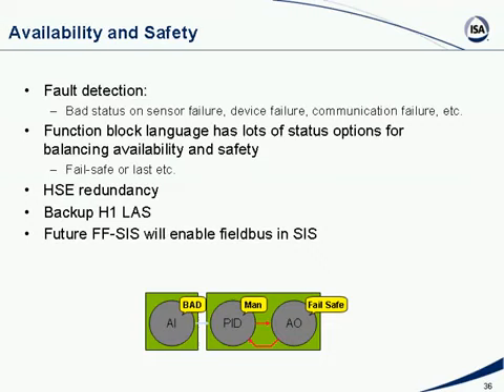Another thing is that usually you have redundant interface cards for field bus, at least for the buses with control. If there's a pure monitoring segment, then maybe you only have a single interface card. Many people only use a single interface card even for control, because there's really not that much that can fail.